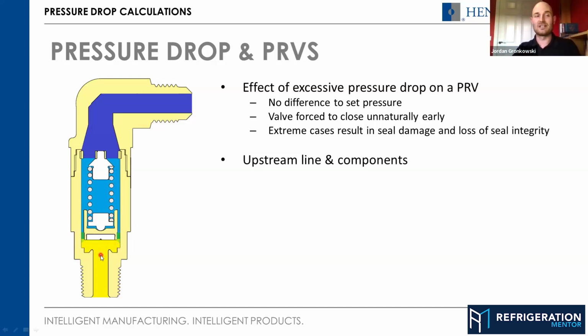So you notice this has changed from red to yellow. It's seen a lower pressure. Because this happens pretty much instantaneously, the valve then wants to close again. And as soon as it closes, the flow stops and the pressure builds up again because of all your built-up back pressure. Then the valve opens and again the cycle repeats. Very similar to what I explained before, and you get this chatter. The piston moves up and down and chatters.